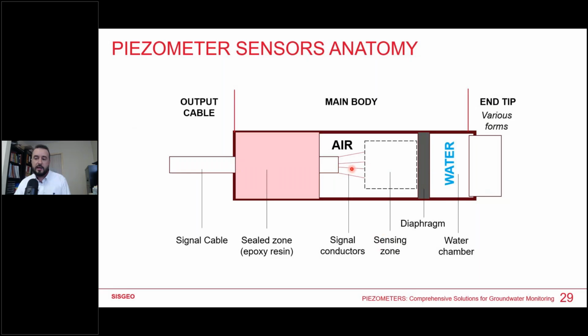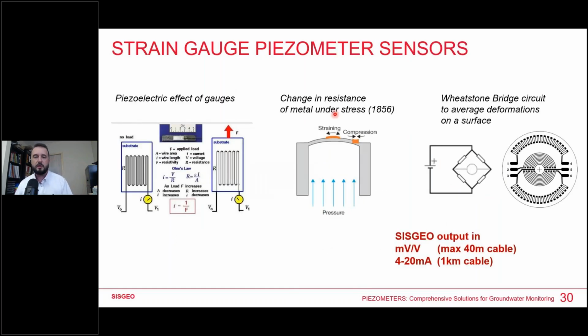The sensing zone is connected to the cable, the output cable, with some signal conductors. And very important, you have this sealed zone. So we use in Sisgeo epoxy resin that allows the electrical circuit to be immersed into water, sometimes 500 meters, sometimes less. So we have to take a lot of care of this part, the sealed zone. So remember this picture. I will remind it for further explanation for a special case.